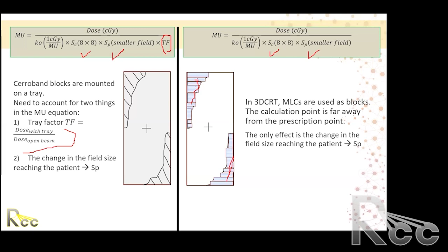Yes, that is actually the core of this lecture. What you are putting in your TPS is fixed geometry, square fields. You are putting in your PDDs measured at certain distances with a flat water phantom. It's all homogeneous. So first of all, you need to do your TPS commissioning thoroughly, right? You have to verify under different geometries, different modifiers, tissue heterogeneity. You have to verify that what your TPS is calculating is equal to what you measure in your heterogeneous phantom. And you can get recommendations from both AAPM and the IAEA.